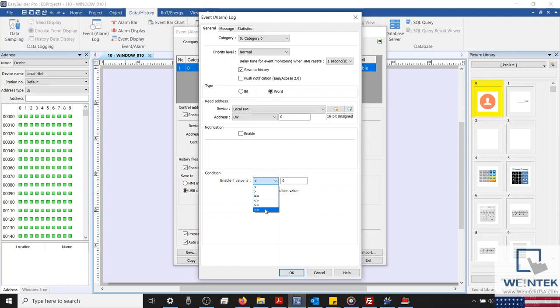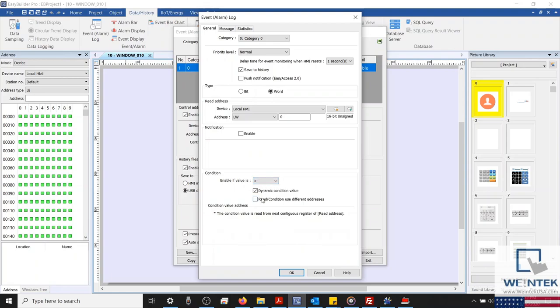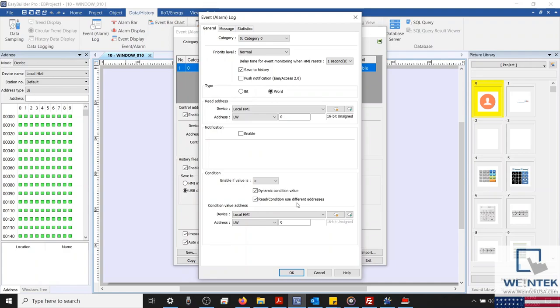The condition value itself can also be changed dynamically from any predefined register. In this example, we'll set our condition to greater than, and we'll give our event a dynamic condition value, which will be read from the next consecutive register after our read address. The only way we can change this to a separate predefined register is if we check Read and Condition Use Different Addresses.